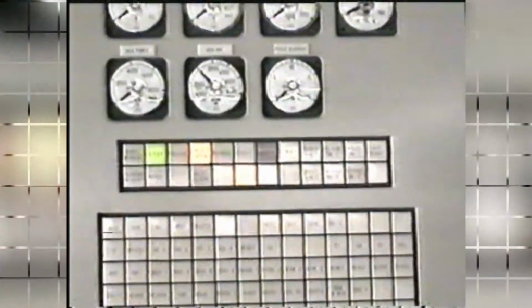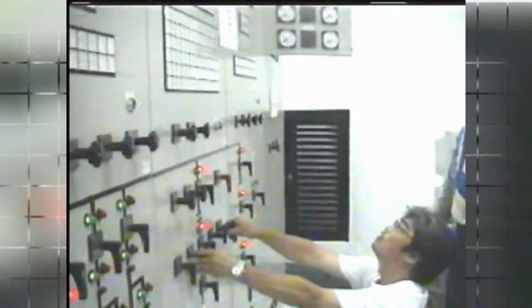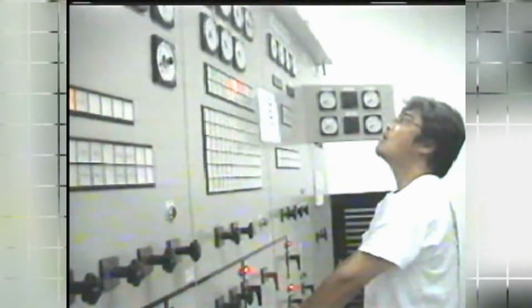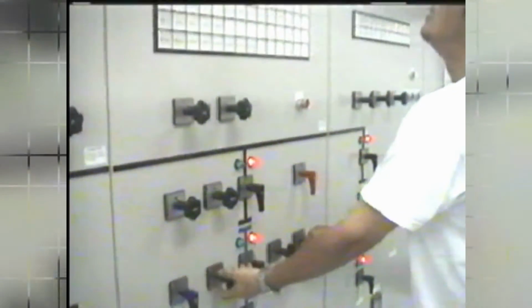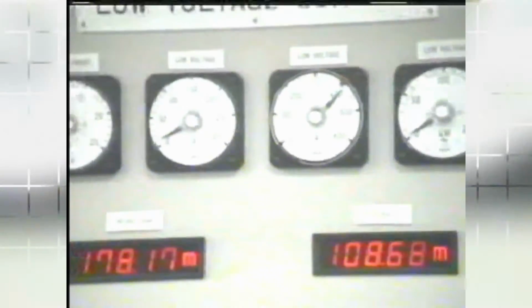One set of automatic synchronizing device is provided for automatic synchronizing of the main generators to the 20 kilovolt power system. The automatic synchronizing device is of static design, consisting of an automatic synchronizer, a voltage balance relay, and a frequency matching device. Interlocks are provided to ensure that only one generator is available for automatic synchronizing operation at a time. The automatic synchronizing control includes automatic control of turbine speed, generator and circuit breaker closing for synchronizing operation with a minimum disturbance to the generator and the power system. The synchroscope is provided with suitable measures to protect the driving mechanism against overheating due to unexpectedly long synchronizing operation.